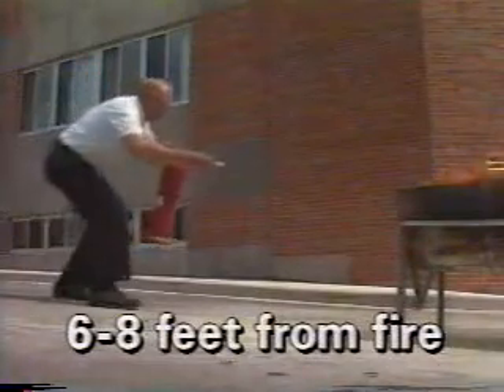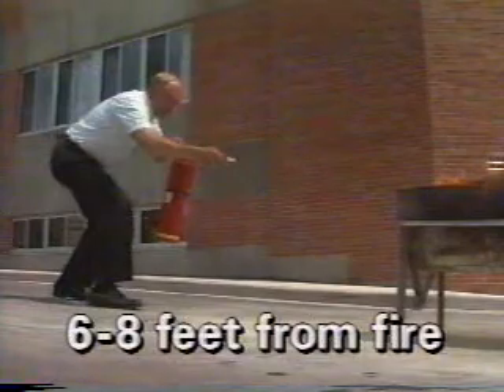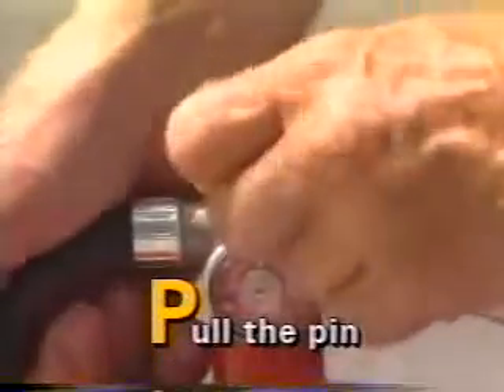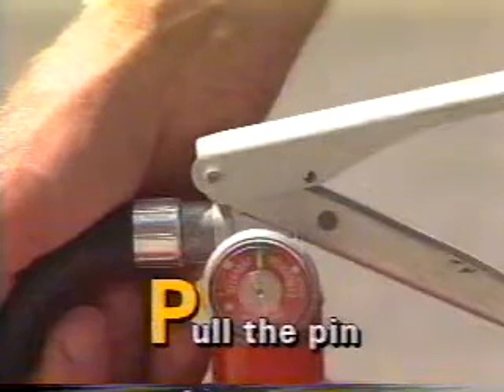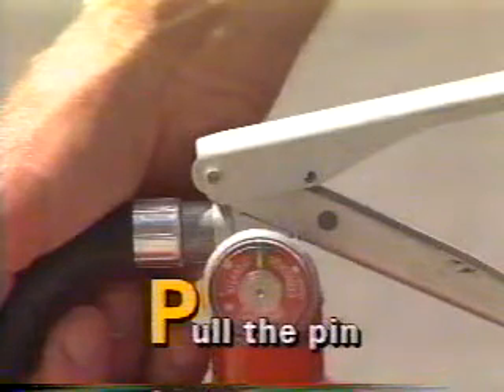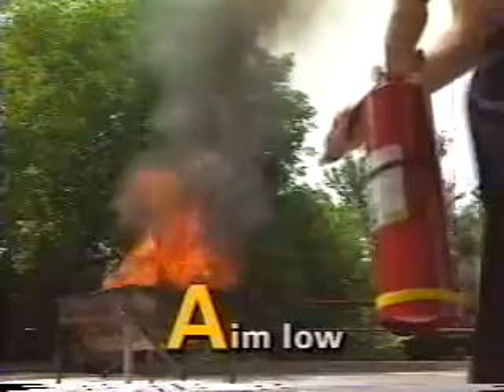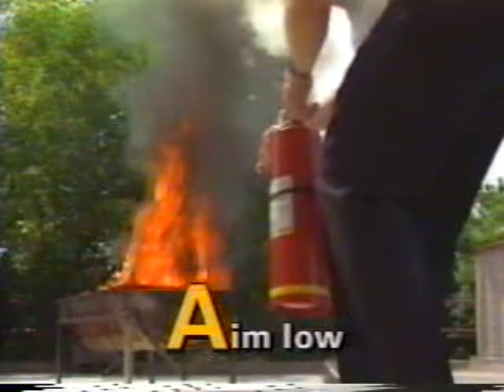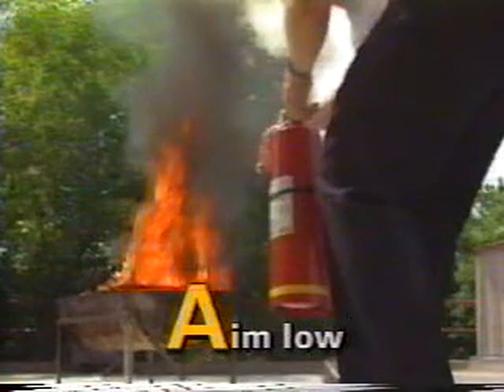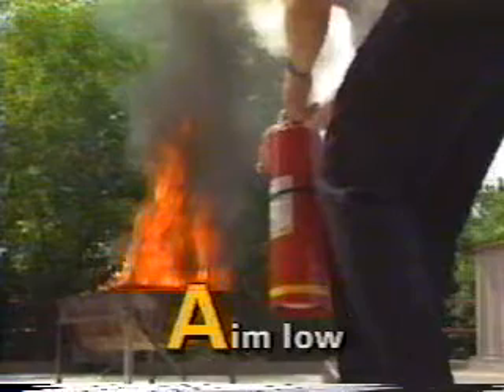To use any portable fire extinguisher, stand at least 6 to 8 feet from the fire, then pull the pin. This will unlock the operating lever so that you can discharge the extinguisher. Now, aim low, pointing the extinguisher nozzle or hose at the base of the fire, where the fire is most intense. Next, squeeze the lever below the handle. Squeezing the lever discharges the contents of the extinguisher. When you let up on the lever, the discharge will stop. Some extinguisher models have a button to press rather than a lever.